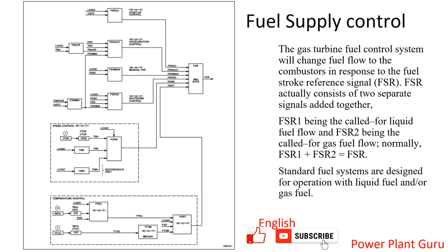Let us first understand what are the different types of FSR which you can see on your gas turbine HMI such as FSR U which is startup, ACC FSR for acceleration, then FSR manual where you want to put a manual control on FSR then you pass any FSR percentage manually. You can give command based on your requirement, that is called FSR manual.